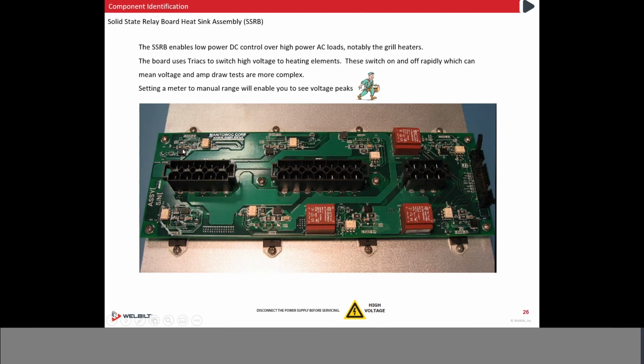If that flash is on continuously, there is no DC control over it. That triac has failed closed and is sending continuous power. It's not pulsating, it's just sending continuous power to that heating zone. If it's off, like you see here, no power is being delivered. Now here's the next thing. If this is off and you see no LED lights, but you see the heating zone still heating, well, there's only one other possibility. Chances are that element is grounded and it is heating that way. Which means the element should be replaced.